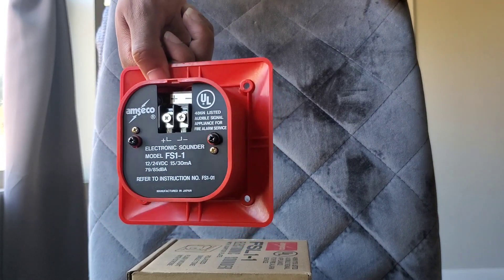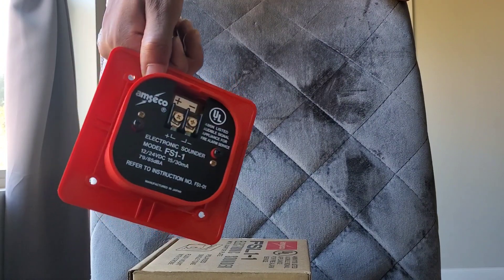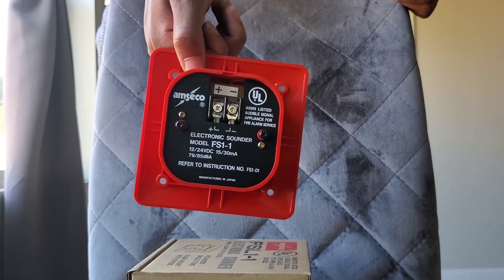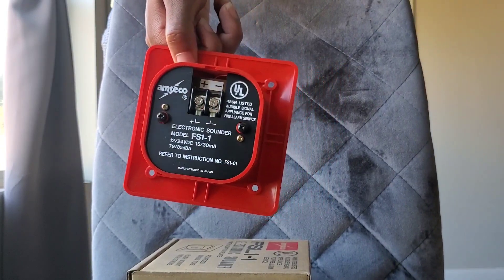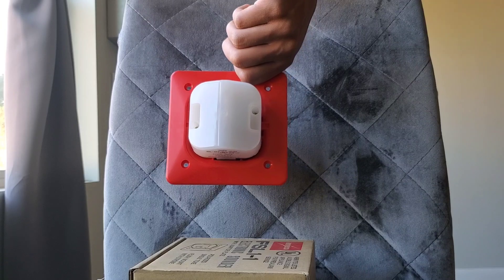...and at 24 volts it's 85 minimum decibels. It's UL listed. And importantly, this whole device is a two-wire device — even though it does not have a strobe. So you can't really do audible silence with this device, which is unfortunate, but it is what it is.